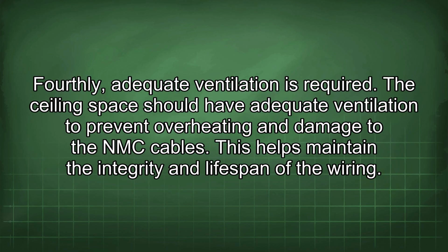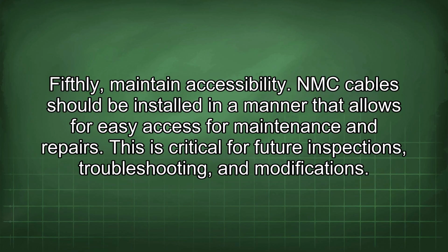Fourthly, adequate ventilation is required. The ceiling space should have adequate ventilation to prevent overheating and damage to the NMC cables. This helps maintain the integrity and lifespan of the wiring. Fifthly, maintain accessibility. NMC cables should be installed in a manner that allows for easy access for maintenance and repairs. This is critical for future inspections, troubleshooting, and modifications.